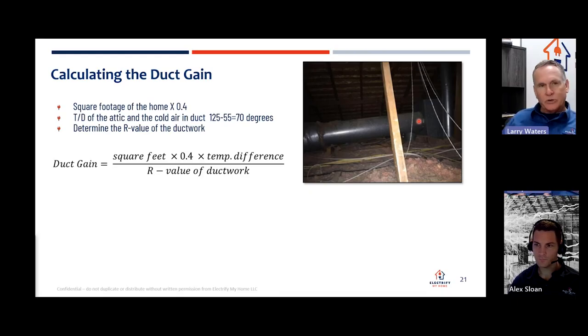So if we pull our return from the house and we run it through our system, we condition it, there's a certain amount of loss that's happening in the ductwork on the supply side in the attic space because of the temperature differential. And we're going to show you how to figure that out. So the way that you figure out duct gain is there is a BPI standard that if we took all the ductwork out of a typical attic, the internal surface area of that ductwork would be about 40% of the square footage of the house.